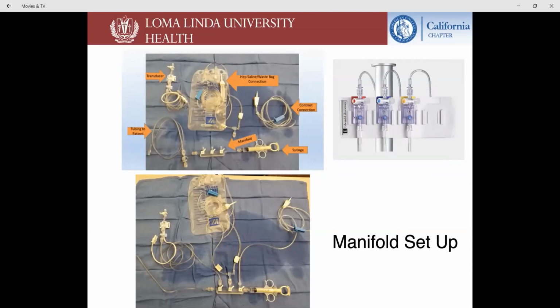It shows three different potential transducers there. The second stopcock connects to your saline flush and waste line. When you draw back the syringe with this stopcock open, it'll pull saline flush that you can use to flush your coronary catheter. If you inject into this line with it open, it goes through a one-way valve to the waste line, so that's where you can dump blood or potentially contrast if you're not using it. And then the third stopcock is to contrast.